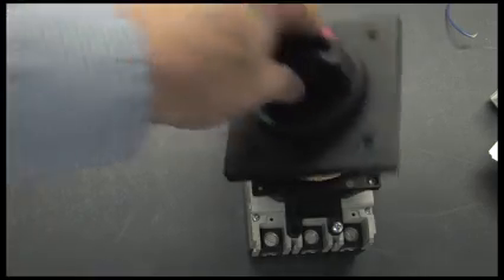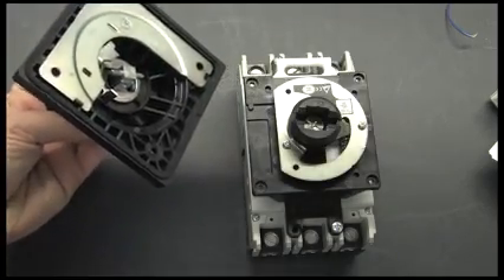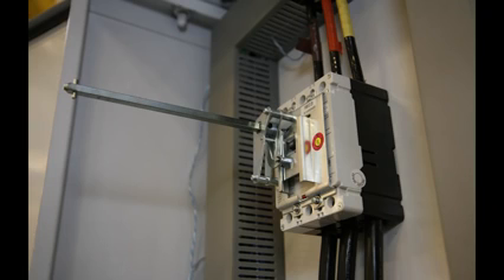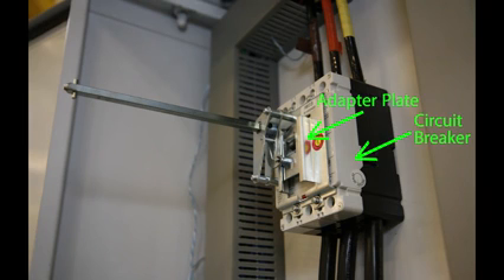Sometimes you need to turn off power before opening a cabinet door, and sometimes it's a requirement. Circuit breakers have 2 ways of doing that. One is this rotary handle, which mounts so that when the door closes, the handle mates up with the circuit breaker adapter directly like this, or using an extension shaft like this one. In both cases, there's an adapter plate that transfers the action to the flipping of the breaker switch.